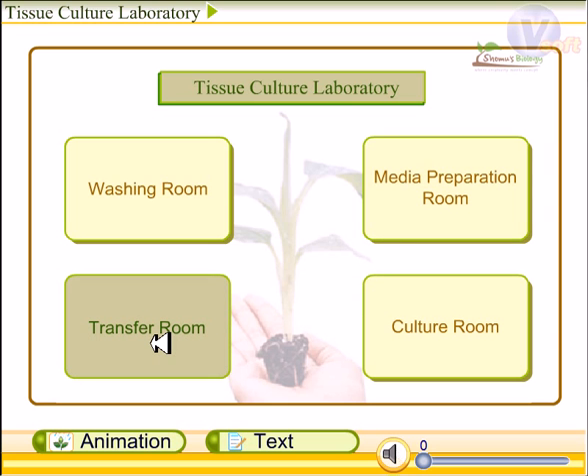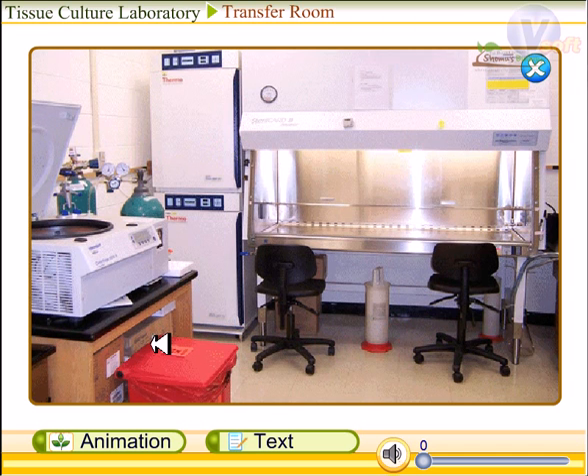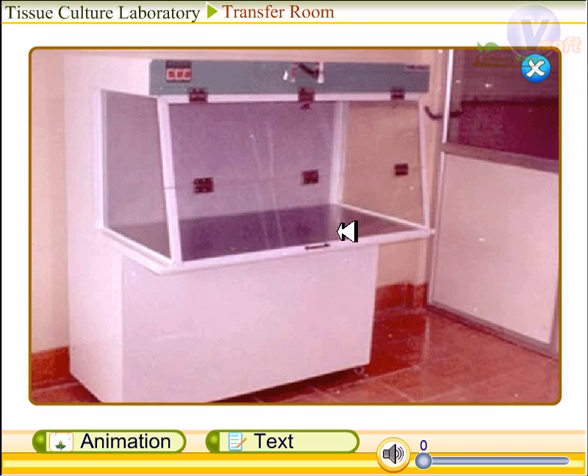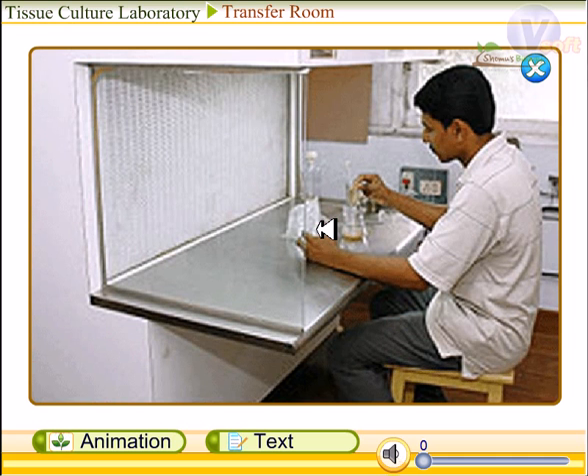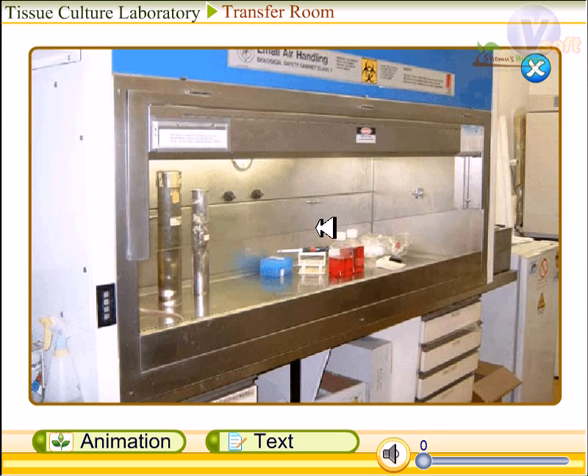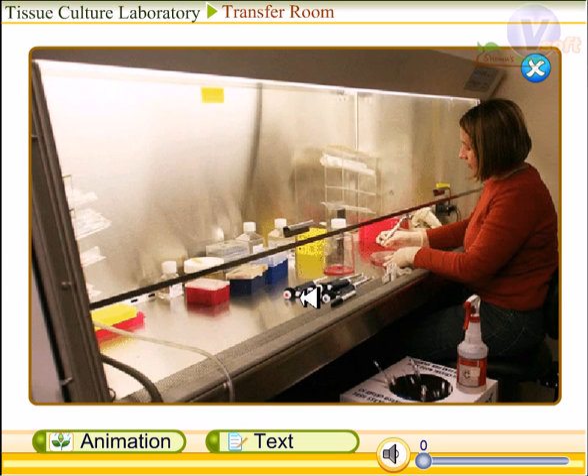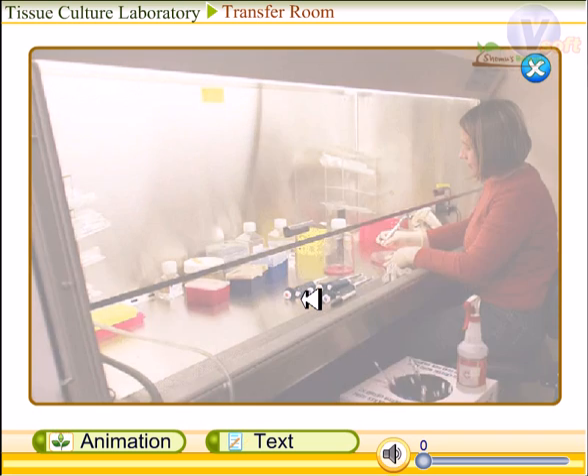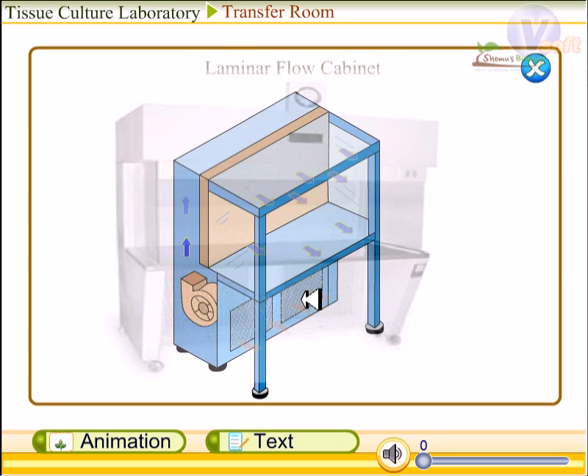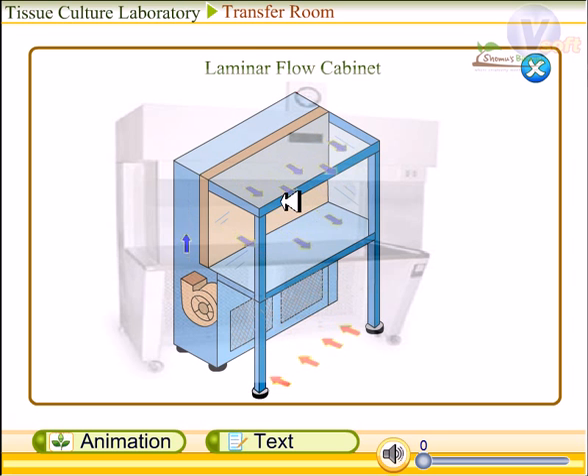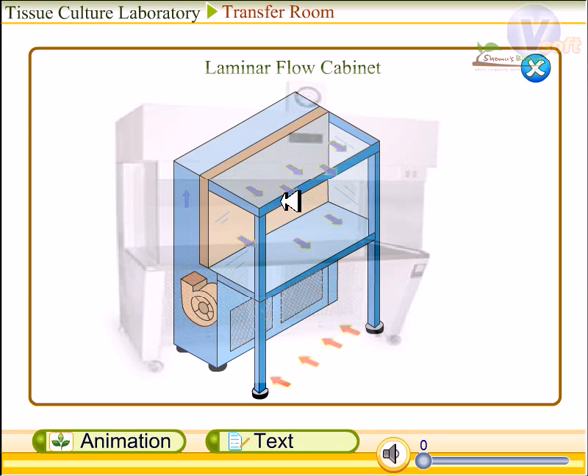Finally, we will look at the transfer room. The transfer room contains a laminar air flow cabinet, which is really important. Air inside the cabinet is continuously exhausted through filters. Zooming into the structure, we can see a continuous flow of air through the cabinet, with filters fixed in the cabinet wall by an air pump installed at the back of the cabinet.